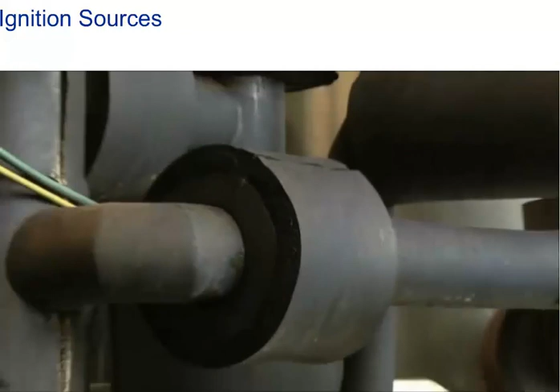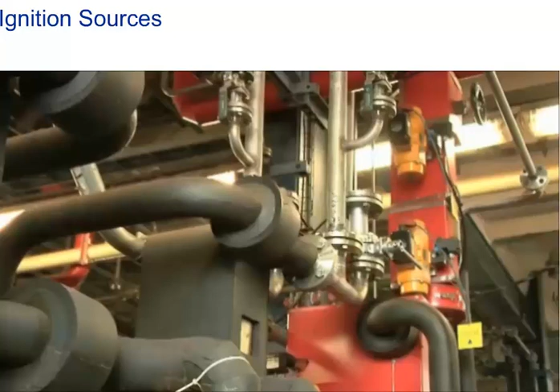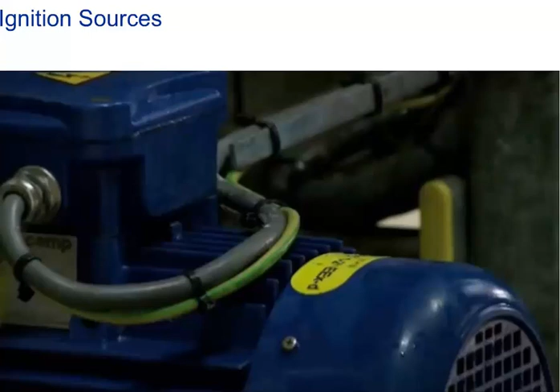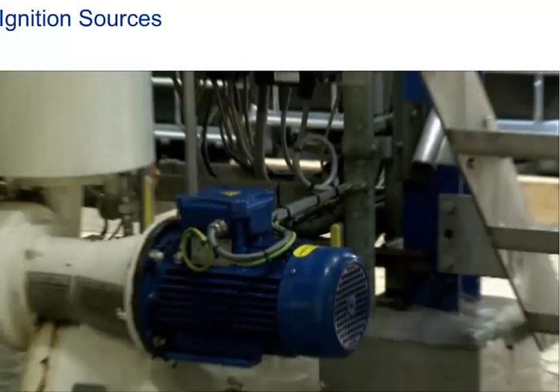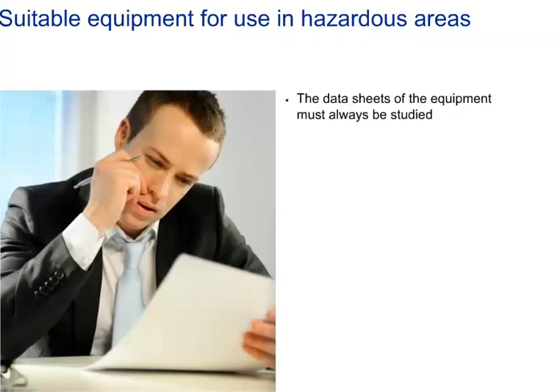Hot surfaces of process lines and electrical equipment can be an ignition source. Insulation is not an adequate protective measure. The surface temperature is not allowed to be above the maximum surface temperature. This temperature is connected to the ignition temperature of the used materials. The data sheets of the equipment must always be studied thoroughly with respect to the gases which may be introduced, and to which additional measures are necessary to create a safe system.